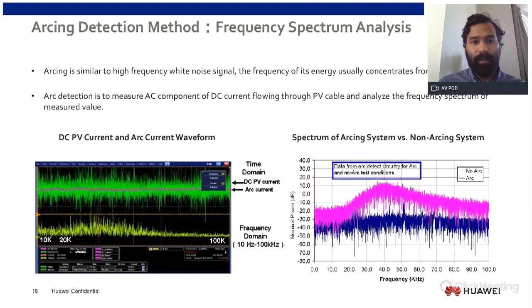However, this is challenging. The other challenge is that, as I was saying before, there will be interference on this signal, and the interference could lead to two problems. First, the solution is missing an actual arc fault situation because of interference. A typical challenge is the attenuation due to the long DC cables. If you have a very long string and the fault is located very far away from the inverter, then the signal will attenuate, and this will make it more difficult to differentiate the case with no arc and with arc.